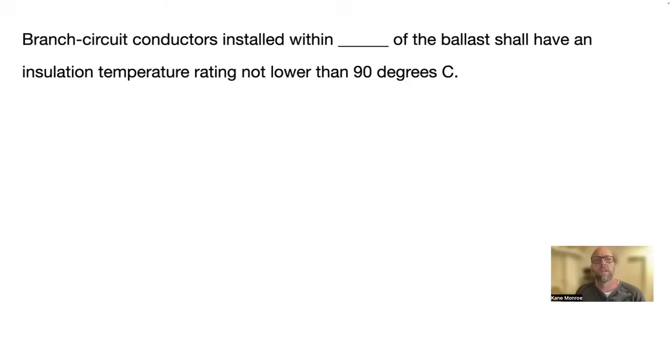All right. Branch circuit conductors installed within blank of the ballast shall have an insulation temperature not rated lower than 90 degrees Celsius. So they're looking for a distance. Three inches. And that's in 410.68. So not within three inches.